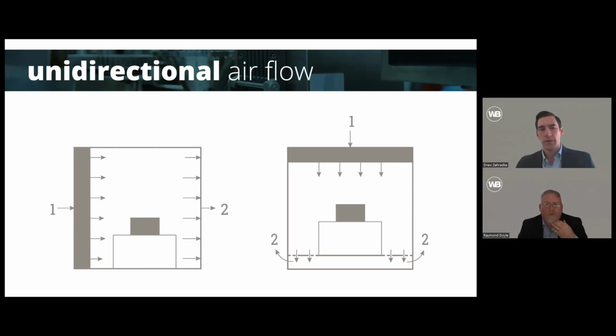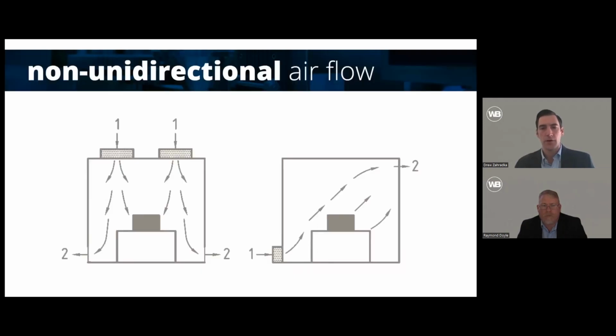Yep, just real quick, with the unidirectional from top to bottom, you'll usually have a raised access floor in this instance. So it's going through the floor, and then it'll pan out to the walls below the room volume. And then the HVAC takes over and ducts it wherever it needs to go. And then in the case where it's probably more commonly seen as non-unidirectional flow, you'd have ceiling HEPA filters and it would go out through a low wall return.